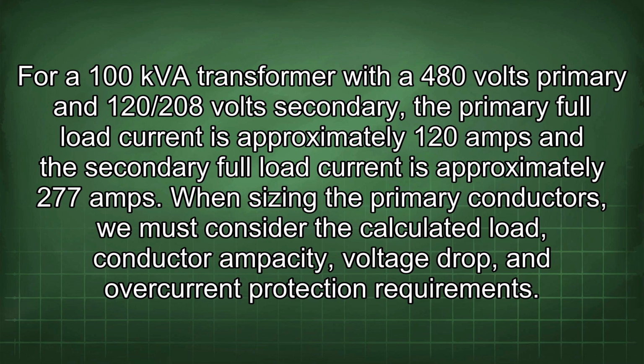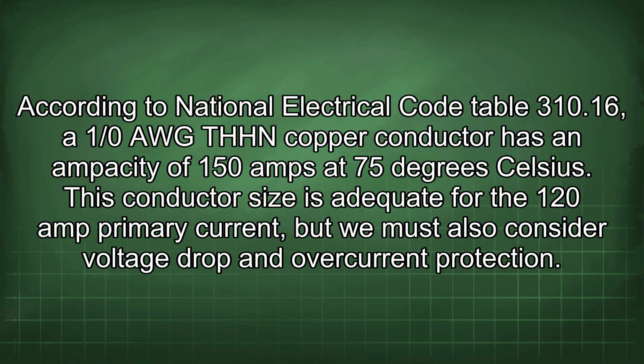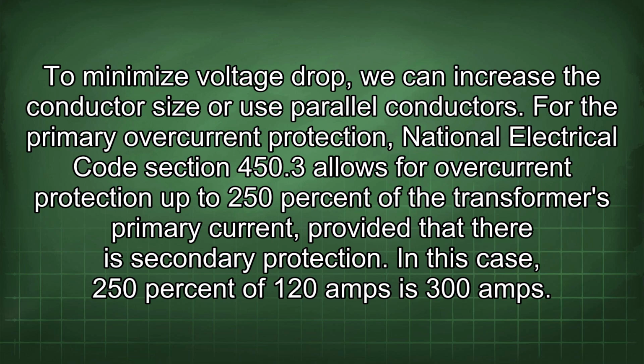277 amps. When sizing the primary conductors, we must consider the calculated load, conductor ampacity, voltage drop, and overcurrent protection requirements. According to National Electrical Code Table 310.16, a 1/0 AWG-THHN copper conductor has an ampacity of 150 amps at 75 degrees Celsius. This conductor size is adequate for the 120 amp primary current, but we must also consider voltage drop and overcurrent protection. To minimize voltage drop, we can increase the conductor size or use parallel conductors.